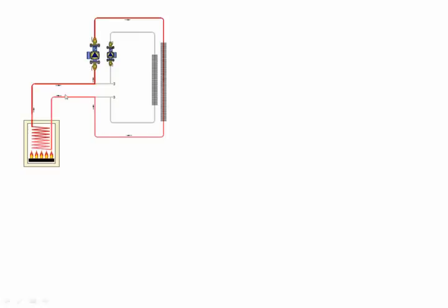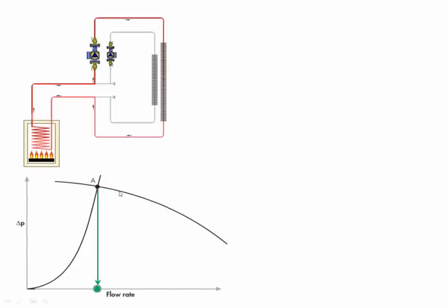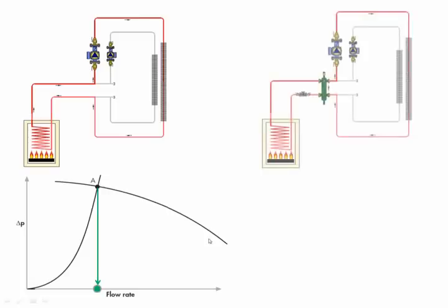Okay? Now, before we put that hydraulic separator in and we sized that pump, we were sizing it to go through the common piping running through the boiler. And if we looked at the curve representing the resistance in this circuit here, we might have gotten a curve like this, and perhaps for the flow rate that we wanted, we would have chosen a pump such as this.